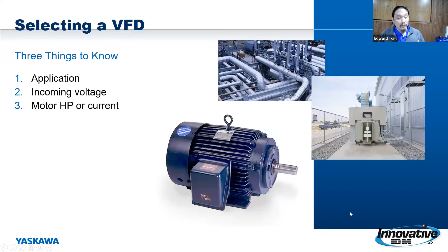Some additional things to consider. One is motor control, the type of motor that you have out there. Right now, the most popular is the induction motor, and that particular motor is something you'll probably find all over your plant. But you might want to pick a drive that has the capability of doing either a permanent magnet or a synchronous reluctance motor. The reason is that those two motor technologies are starting to emerge more and more, and you may find that there could be a shift toward using those versus the induction motor for the energy efficiency.